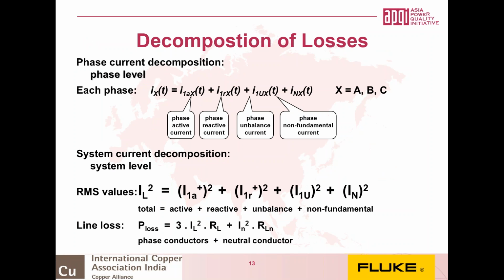So the unified method does something somewhat different from the other methods. We effectively decompose the current. Here we have small i and large I. The small i are instantaneous values and the big I are the system values. For each of the phases we can break down the losses into separate components. Here they're called IX, where X is the name of the feeder: A, B, C, or L1, L2, L3. And we break these down into the phase active current, the phase reactive current, the phase unbalanced current, and the phase non-fundamental current, non-fundamental being any harmonics, for example.